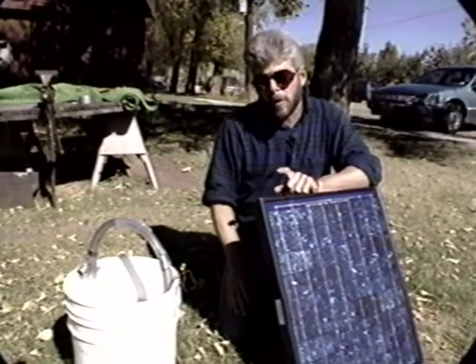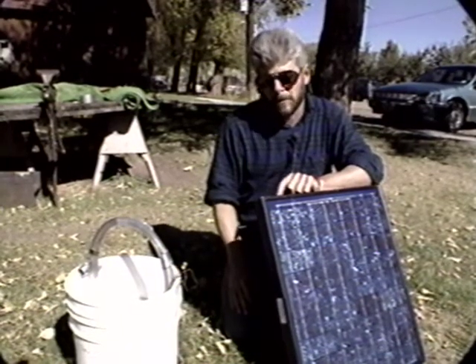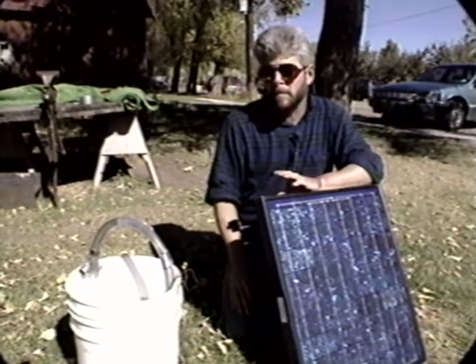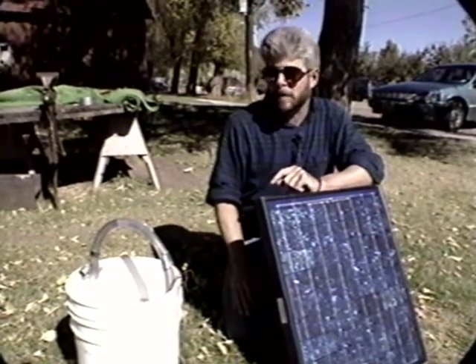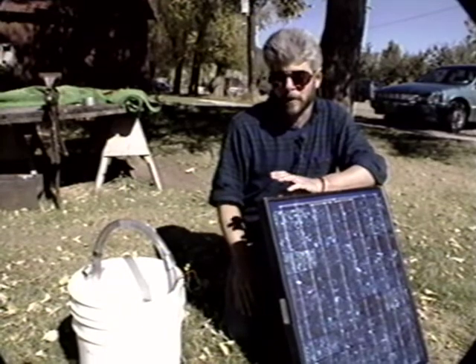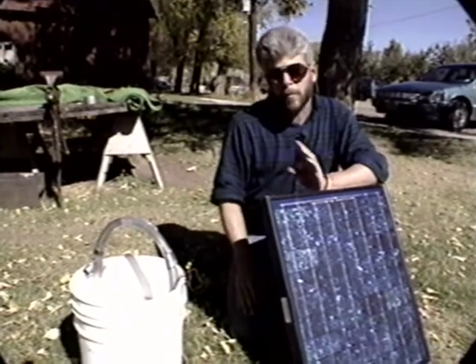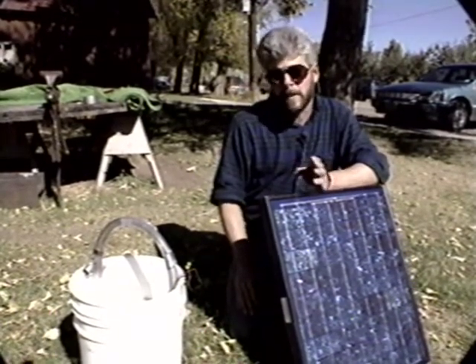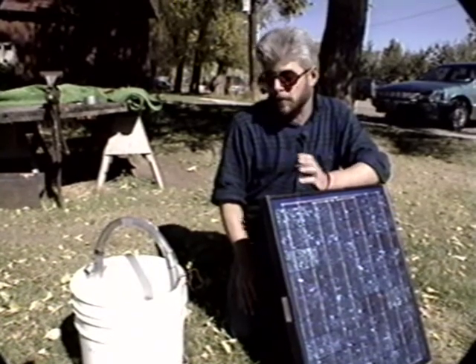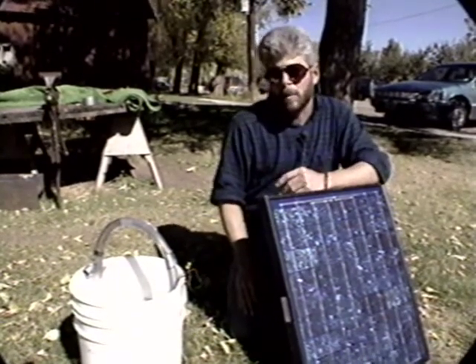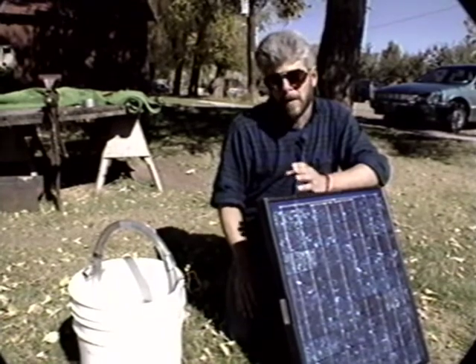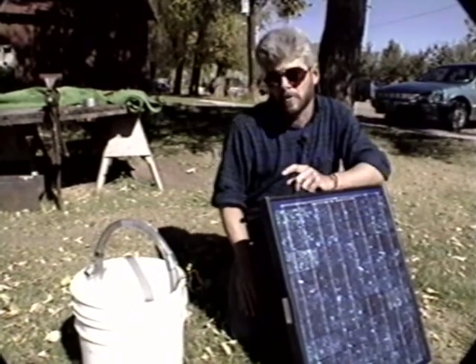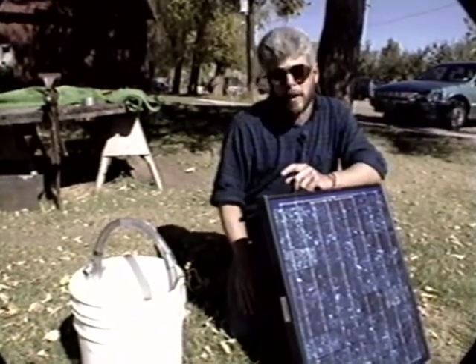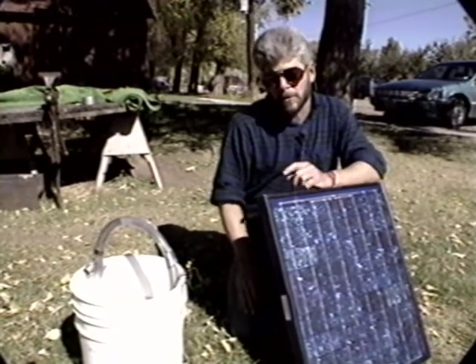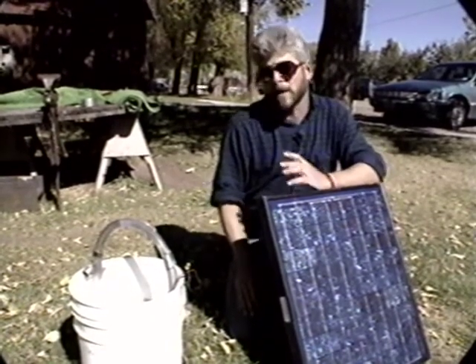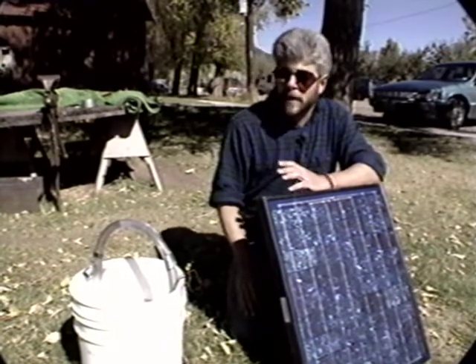There are some rules of thumb we follow for mounting PV modules. Number one, keep them unshaded from 9 in the morning to 3 in the afternoon throughout the year. Number two, face them at the optimum orientation—in northern latitudes, that's any place above the equator, we want to face our modules true south, where the sun is in the sky at solar noontime. Our third rule of thumb says we should mount the modules at a tilt angle equal to our latitude for best year-round performance.